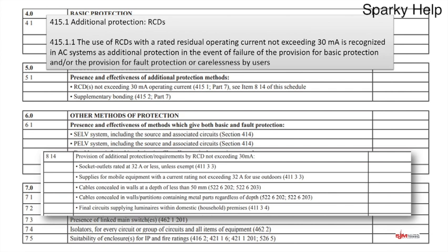So if you're going to put one in, what have you put it in for? Is it for sockets that are 32 amp or less? Is it for mobile equipment? Is it because your cables are concealed in the walls? Is it because your cables are in walls that have metal partitions? Or is it the final circuit supplying luminaires within domestic household premises?